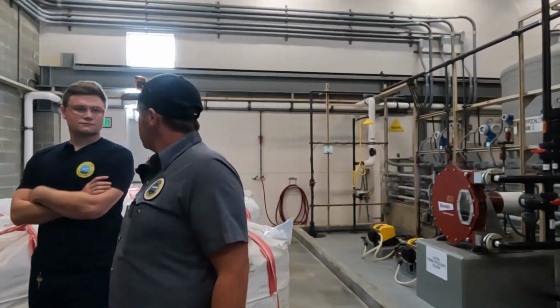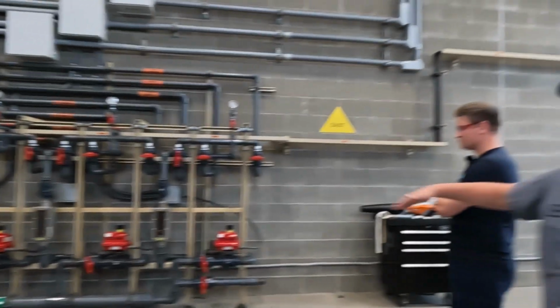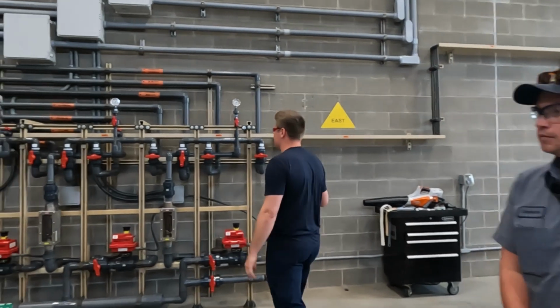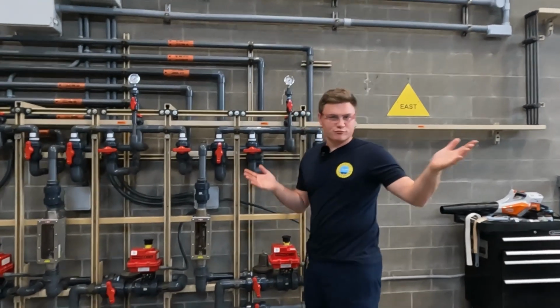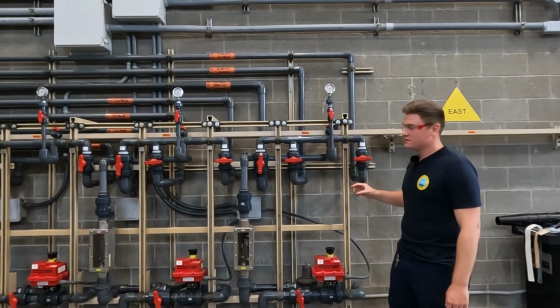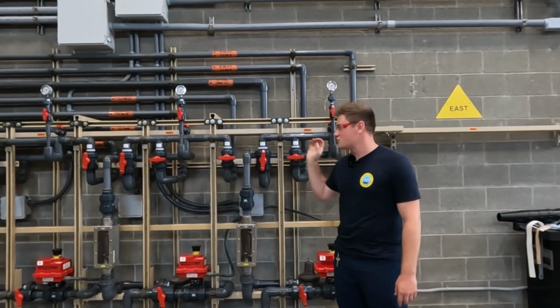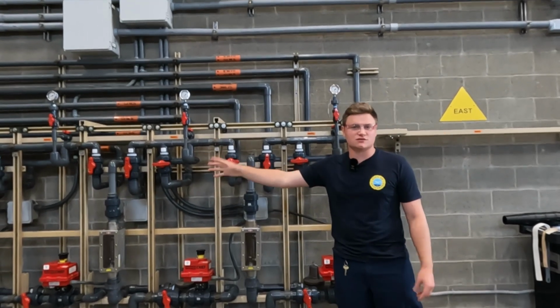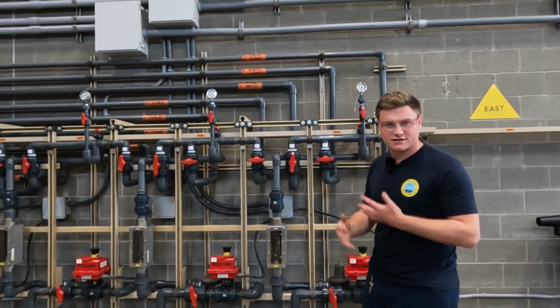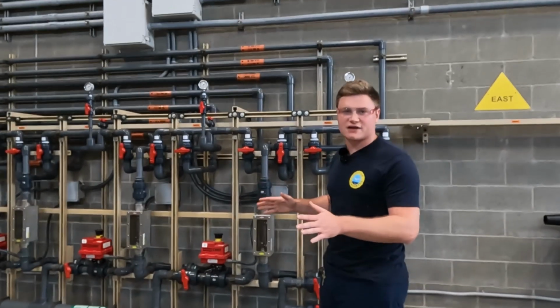There's the actual chlorination going through these valves, and then we are able to regulate our feed flow through here. So basically how this manifold works is your sodium hypochlorite, or bleach, is injected into a water system right at this location. And so that makes it so you can send bleach in water to a location instead of just a full line of bleach all the way out to different locations throughout the plant. So it adds a little safety factor. It helps with the mixing of the chlorine into the water, make sure everything's all mixed up, and it helps us meter it and make sure we're dosing it accurately and precisely.